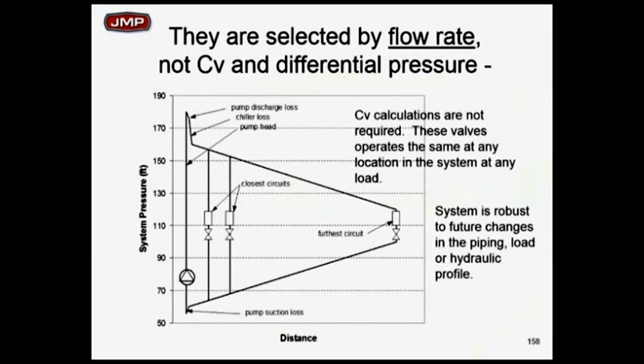And if you do that, the same valve authority out to the end and for the valves in close to the chiller plant, the valves in close to the chiller plant become just on-off valves. They don't even modulate. Pop up a little bit, probably going to eat them up. In other words, you're losing control of those valves. You have very little valve stroke. You're going to lose delta T control on them. They're going to have a tendency to take more water flow than designed.